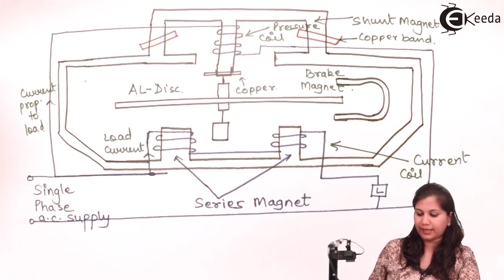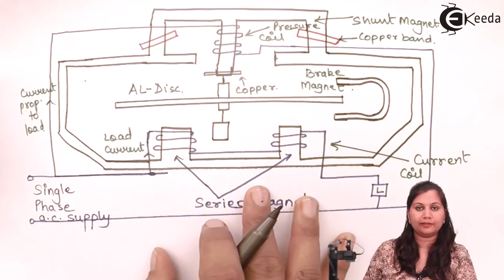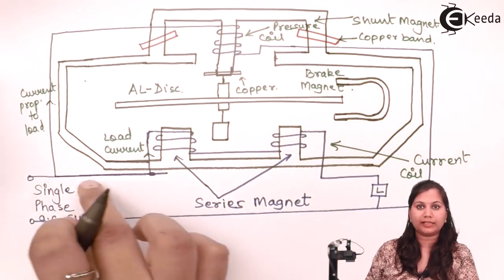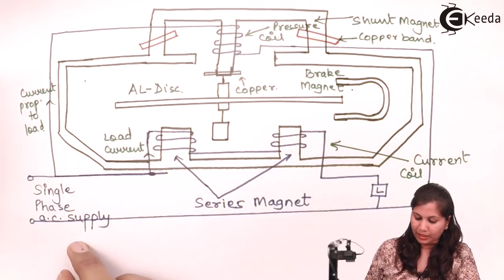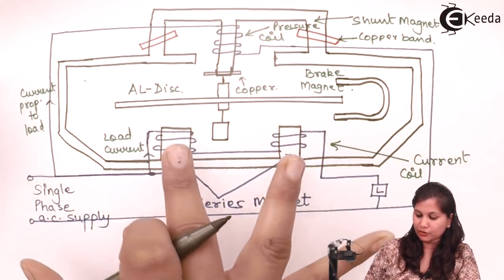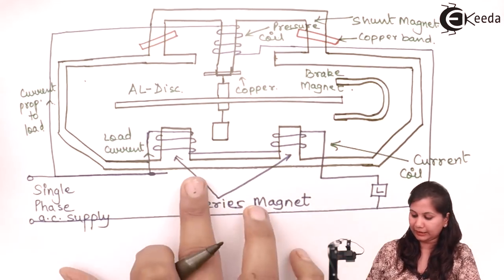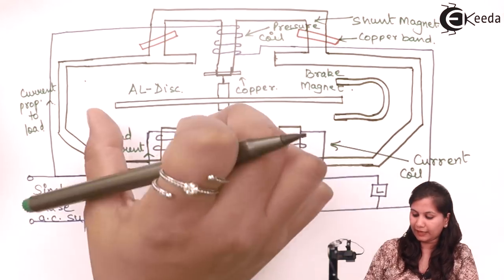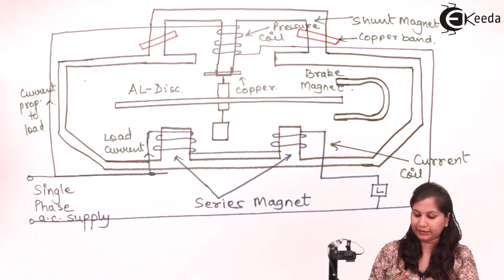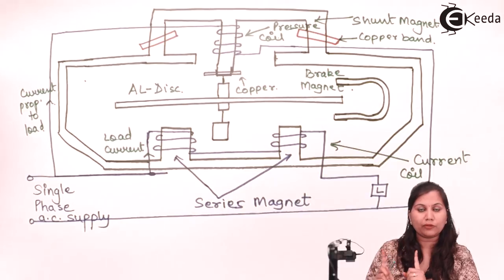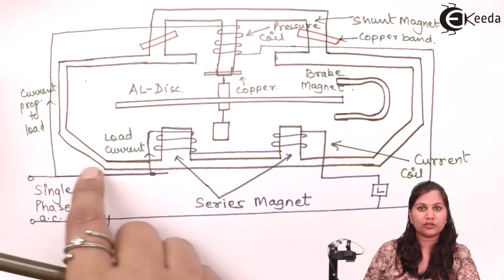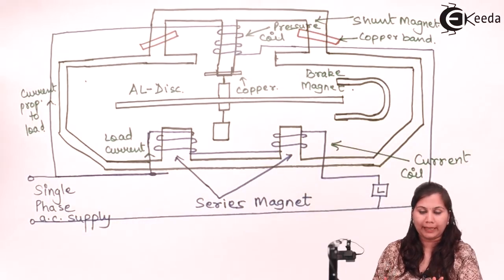This is the diagram for the single-phase induction type energy meter, with a single-phase AC supply. It consists of two electromagnets — one is the shunt magnet and the other is the series magnet. In between these two magnets is the aluminum disc, which rotates in the magnetic field. The speed of rotation of this disc is proportional to the power consumed by the appliance.